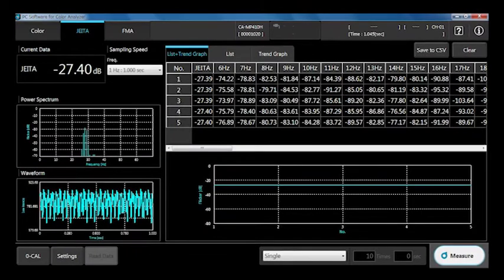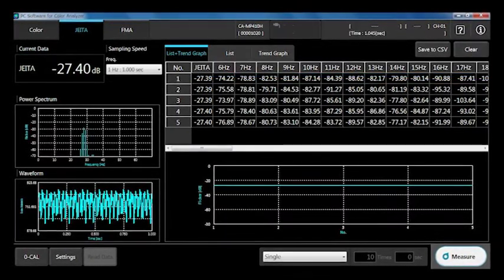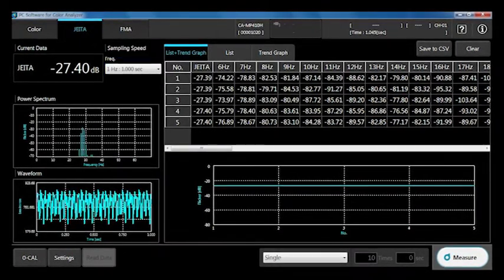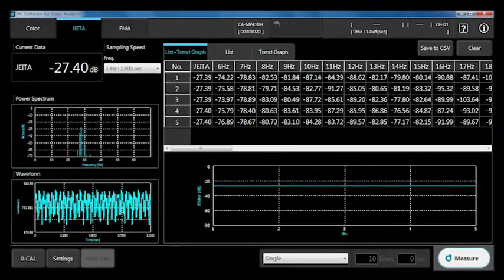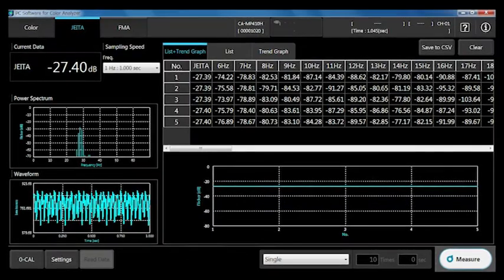The CA-410 measures both JEITA and contrast flicker present in newer displays. The expanded frequency measurement range and adjustable frequency response allows accurate characterization of today's modern cutting-edge display technology, including luminance and color characterization of HDR displays.